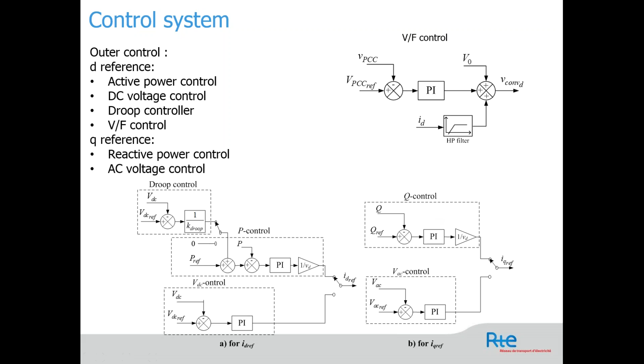Then you have the circulating current control. This control loop is in the lower level control, and it is related to the MMC topology. It is already known that the MMC will generate a negative sequence current with a second harmonic. So in order to make it work, you need an additional control for this negative sequence current, which will generate losses in the station and can also generate instability.